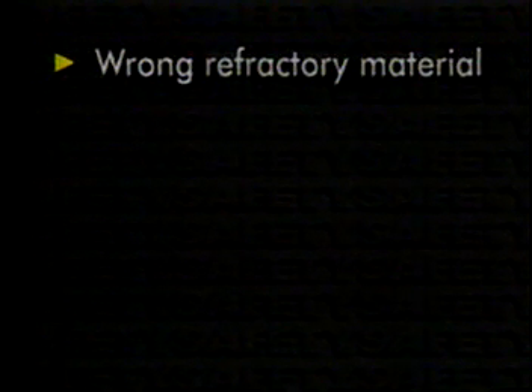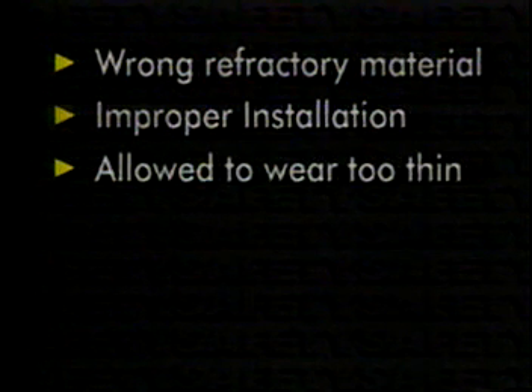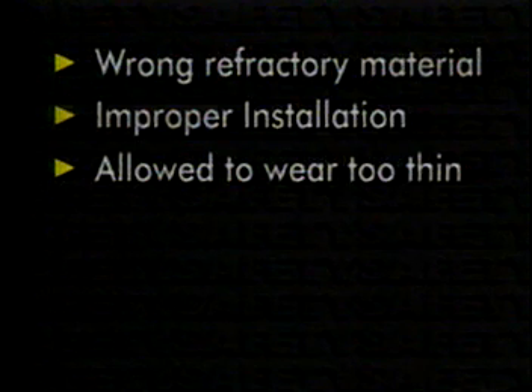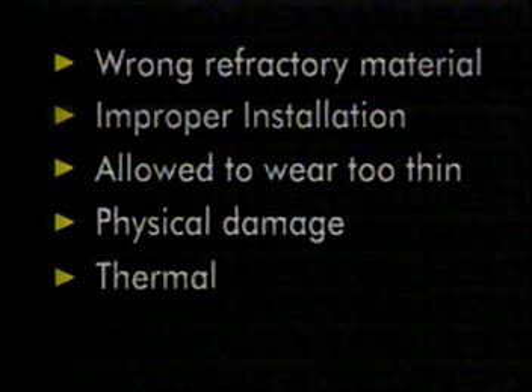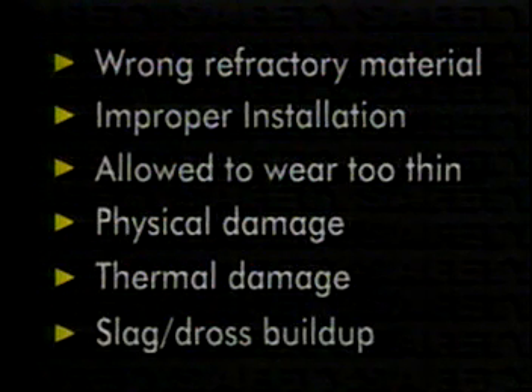The wrong refractory material was used for a particular application. The refractory was inadequately or improperly installed. The normal lining wear produced by the inductive stirring of the metal was not monitored, and the lining was allowed to become too thin. Physical shocks or mechanical stress damaged the lining. Excessive temperatures or thermal shocks damaged the lining. And finally, slag or dross was allowed to build up. Any one of these situations can result in a metal runout from an induction furnace. Let's look at each in more detail.